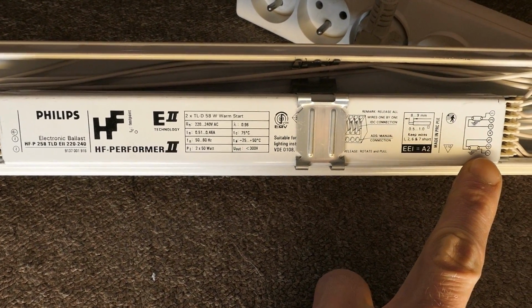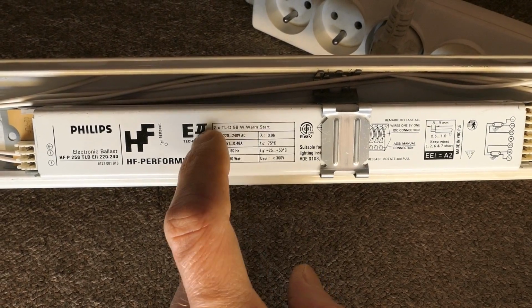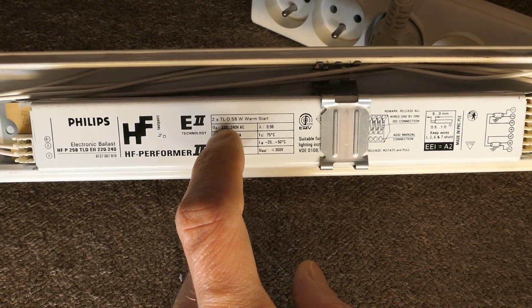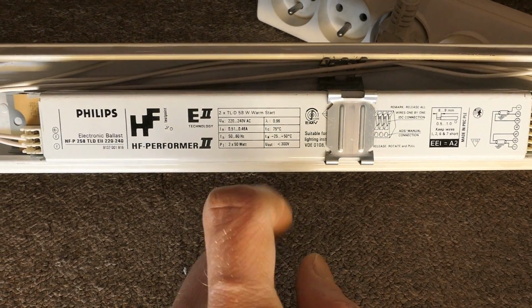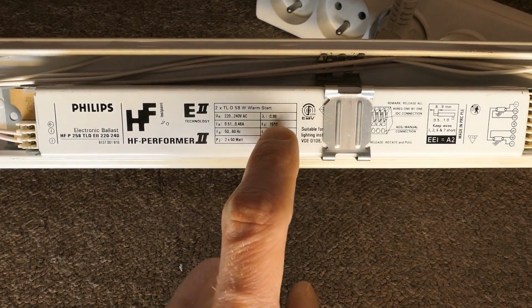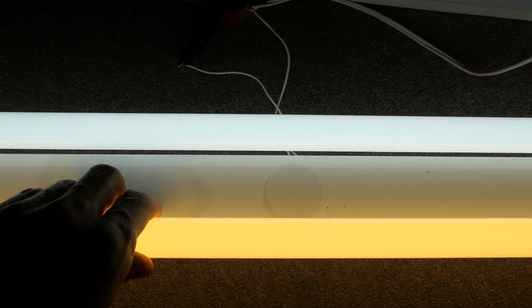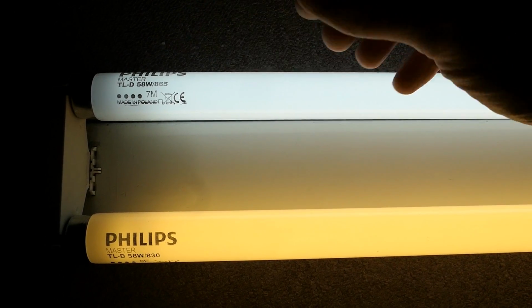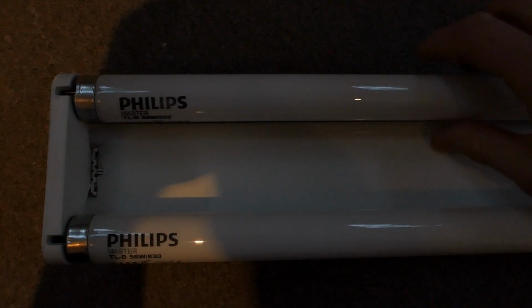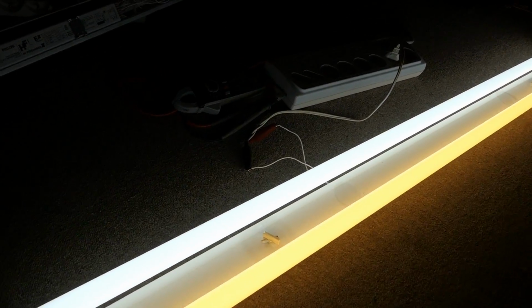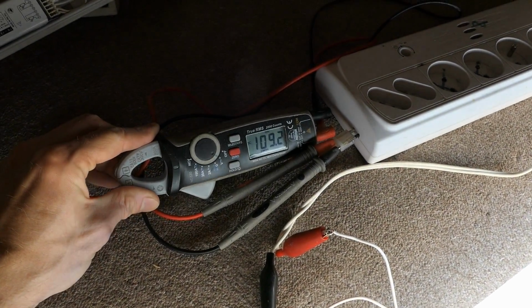Here's the wiring, and they're in series. 58 watts, 2 times, warm start, 220 to 240 volts, almost to unity power factor 0.96. And I guess if I remove one of the tubes, the other one will go out because it's in series. Yes. So if one tube fails, the entire thing stops running. This is a disadvantage in comparison to a double tube magnetic ballast fixture. But it's more efficient and flickerless.